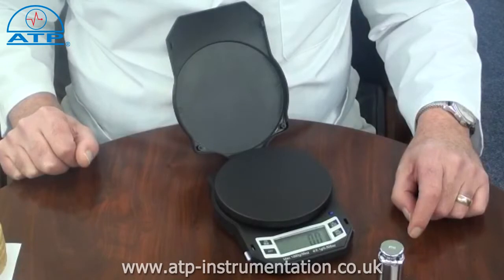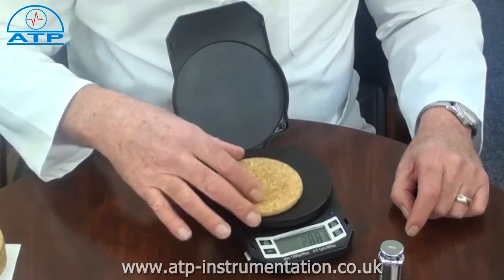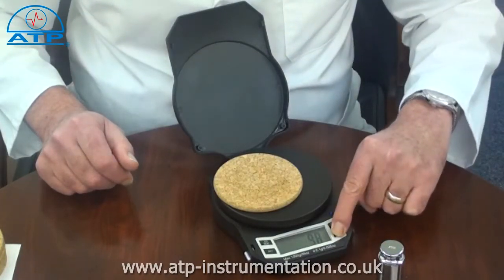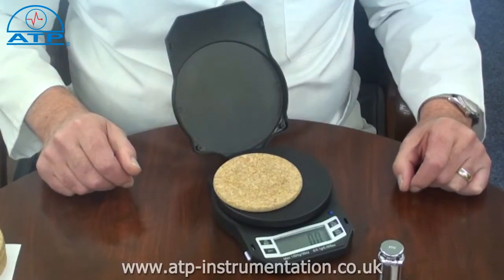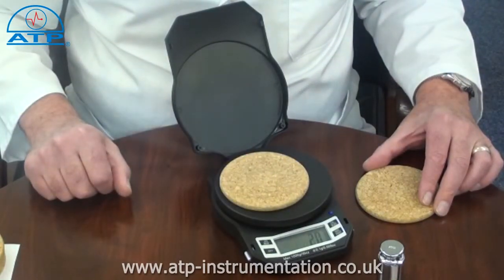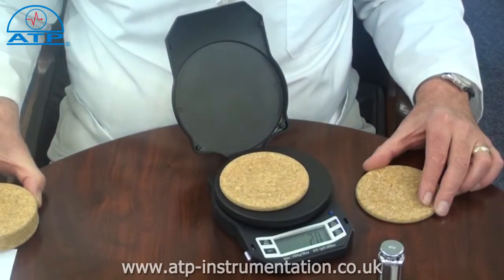Plus or minus weighing is ideal for quality control applications such as sample cross-checks. Simply take a product or a calibration weight and place it on the platform, then press tare. The displayed value will be zero. Remove the sample or weight and then place another sample on the pan. If there is a difference in weight, the displayed value will be the difference, shown as a plus or minus value.